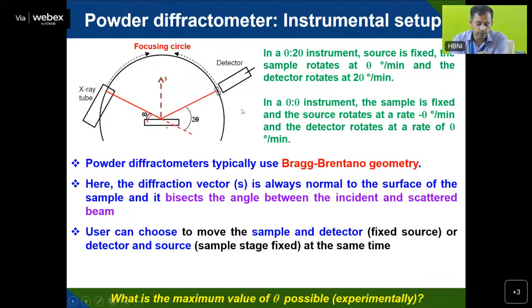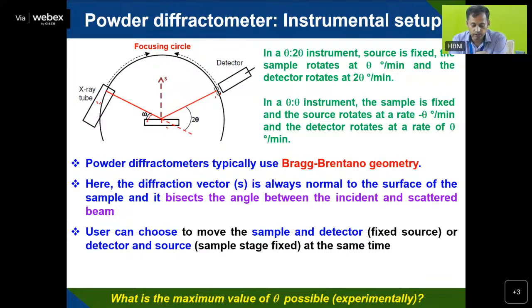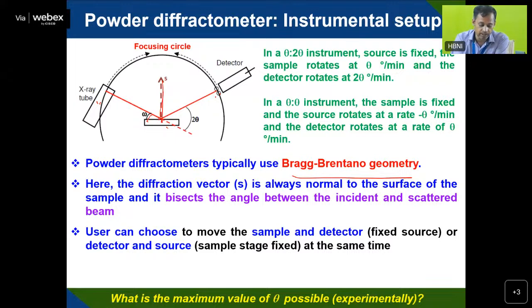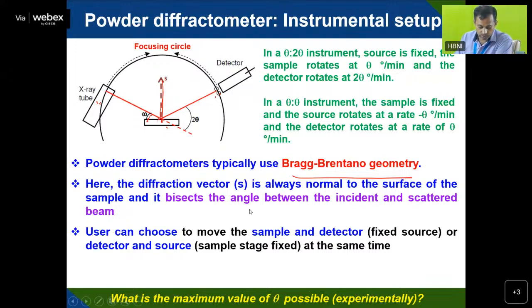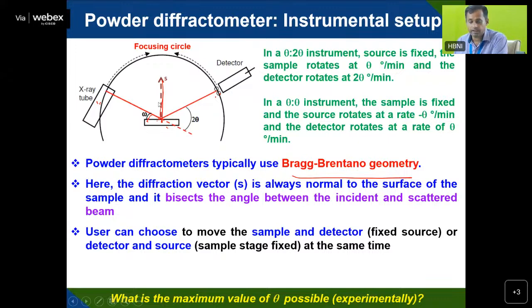In Bragg-Brentano geometry, the X-ray tube and detector are on the surface of the focusing circle, with the sample at the center. The user can choose to move the sample and detector, or the detector and source, based on the sampling process. The maximum θ is theoretically 90 degrees, but experimentally it is very difficult to go beyond 70–80 degrees.